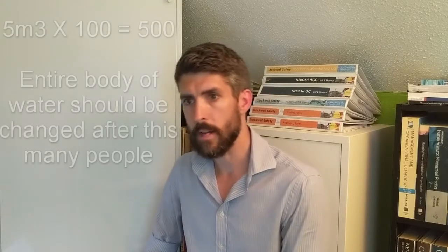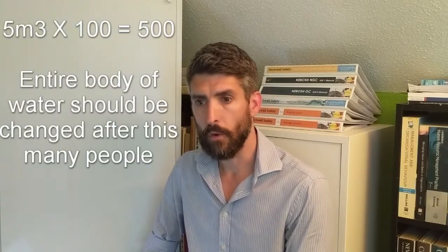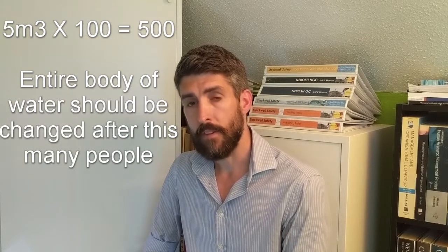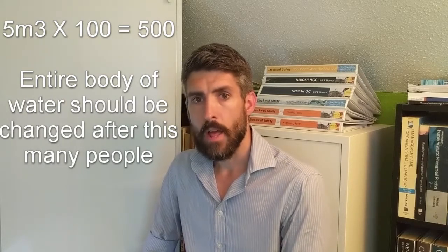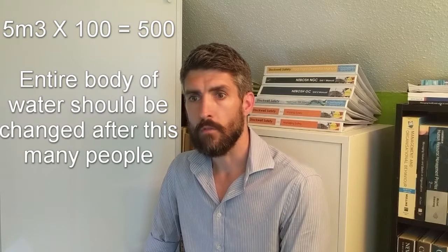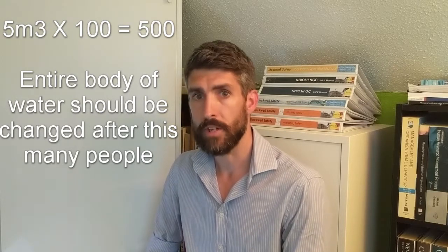The next thing to think about is the amount of dilution, the amount of fresh water coming in. And it's worked out in a similar sort of way. You look at the volume of water again, but this time you're multiplying it by 100, and in this instance, if we're talking about a spa pool that's got 5 cubic meters, 5 times 100 is 500. So after 500 bathers, you should have looked to have replaced the entire body of water with fresh.